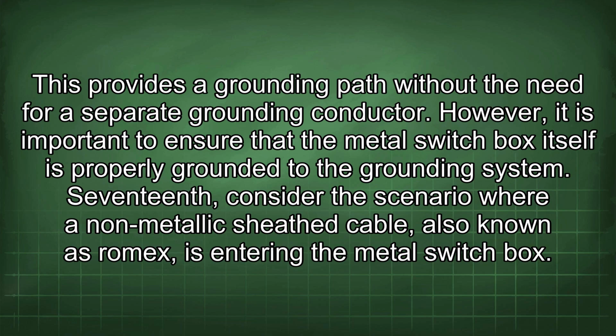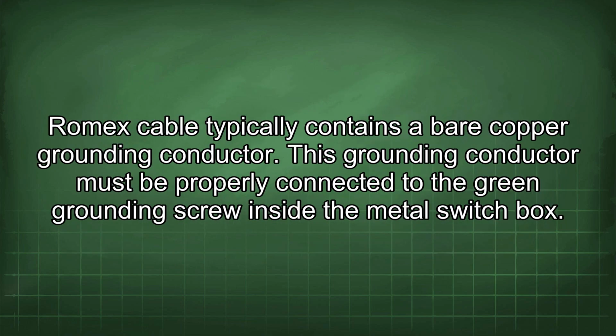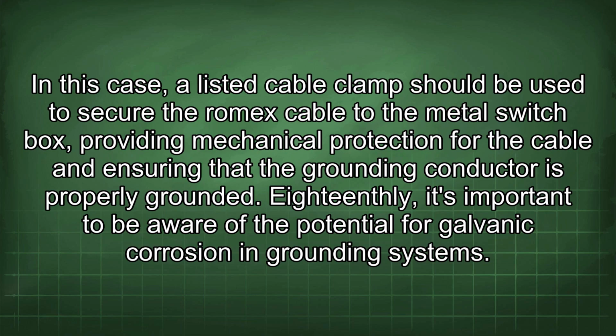17th, consider the scenario where a non-metallic sheath cable, also known as Romex, is entering the metal switch box. Romex cable typically contains a bare copper grounding conductor. This grounding conductor must be properly connected to the green grounding screw inside the metal switch box. In this case, a listed cable clamp should be used to secure the Romex cable to the metal switch box, providing mechanical protection for the cable and ensuring that the grounding conductor is properly grounded.